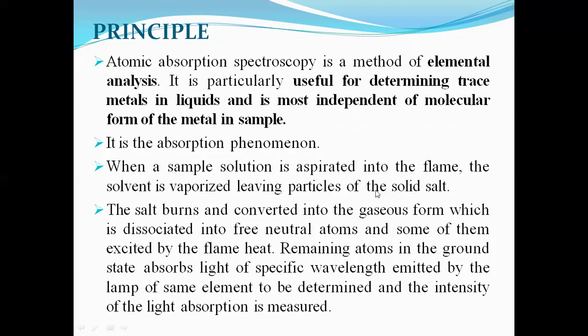When the sample solution is aspirated into the flame, the solvent is vaporized, leaving particles of the solid salt. This solid salt burns and is converted into gaseous form, dissociated into free neutral atoms. Some of them are excited by the flame heat. The remaining atoms in the ground state absorb light of specific wavelength emitted by the lamp of the same element to be determined, and the intensity of the light absorption is measured.